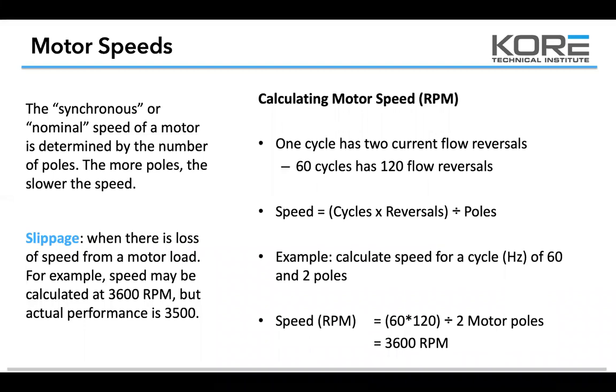The motor speed calibration tools are quite expensive. I know of 2 guys in the company that have them, and we've used them a couple times, but it's not necessarily necessary. But if you think you have a motor with a tremendous amount of slippage, then let us know. We can help out with that, or when in doubt, get it rebuilt or change it out. So if it's causing sporadic problems because the slippage is quite a bit and the motor's fairly old, then you're probably going to end up just changing that motor.